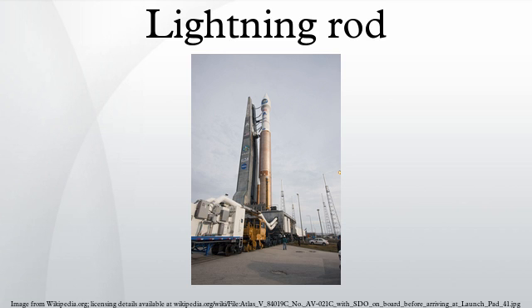A modeling system based on a better understanding of the termination targeting of lightning, called the rolling sphere method, was developed by Dr. Tibor Horváth. It has become the standard by which traditional Franklin rod systems are installed. To understand this requires knowledge of how lightning moves. As the step leader of a lightning bolt jumps toward the ground, it steps toward the grounded objects nearest its path. The maximum distance that each step may travel is called the critical distance and is proportional to the electrical current. Objects are likely to be struck if they are nearer to the leader than this critical distance.